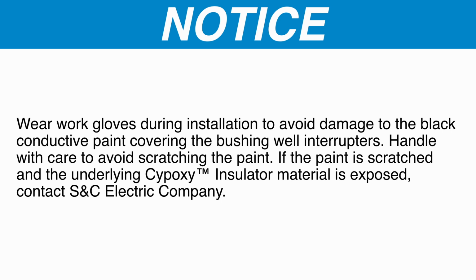Notice: wear work gloves during installation to avoid damage to the black conductive paint covering the bushing well interrupters. Handle with care to avoid scratching the paint. If the paint is scratched and the underlying Cypoxy™ insulator material is exposed, contact S&C Electric Company.